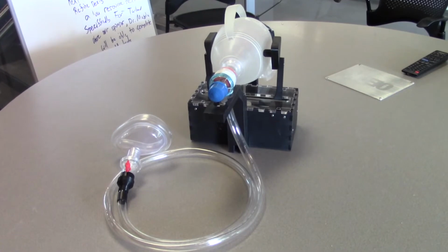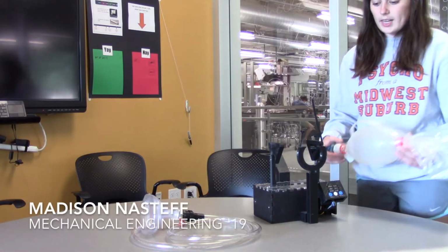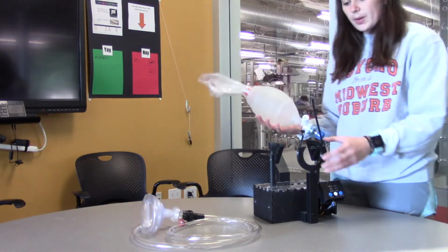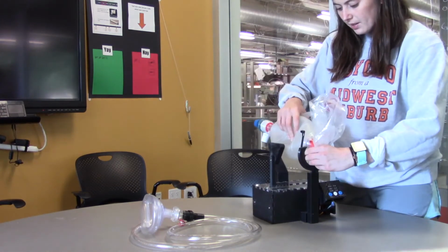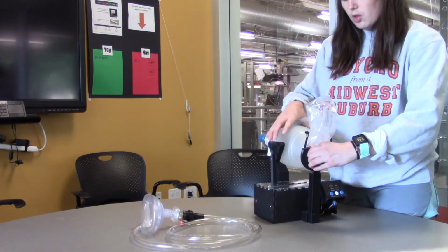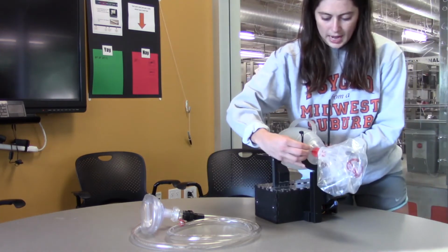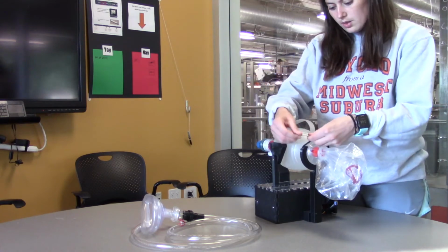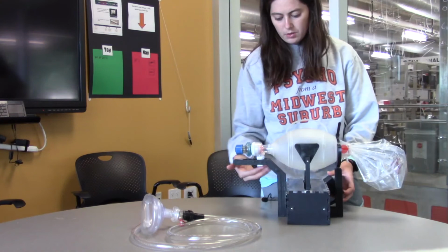And now we will go through how the device works. The first step in our process is attaching the bag valve mask to our device. In order to do so, we have a back attachment and a front attachment. You simply put the bag in, squeeze it a small amount to get it inside the compression, and then snap the back on like so. You attach it like this, and then the front will slide into one of these 4 holes.